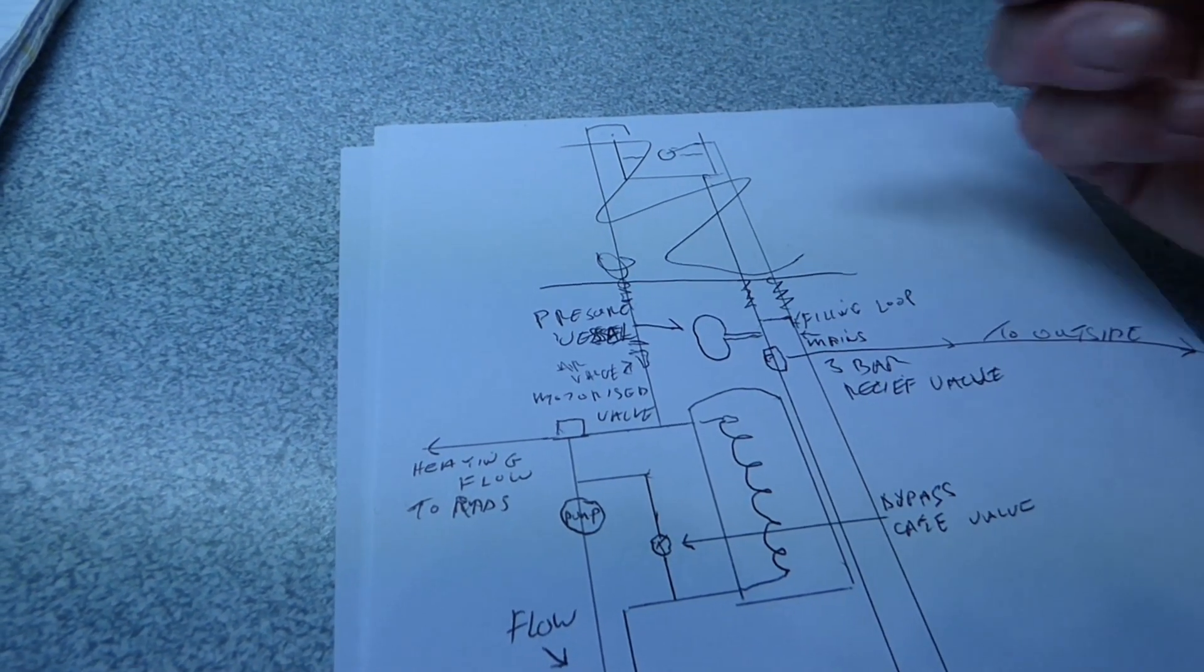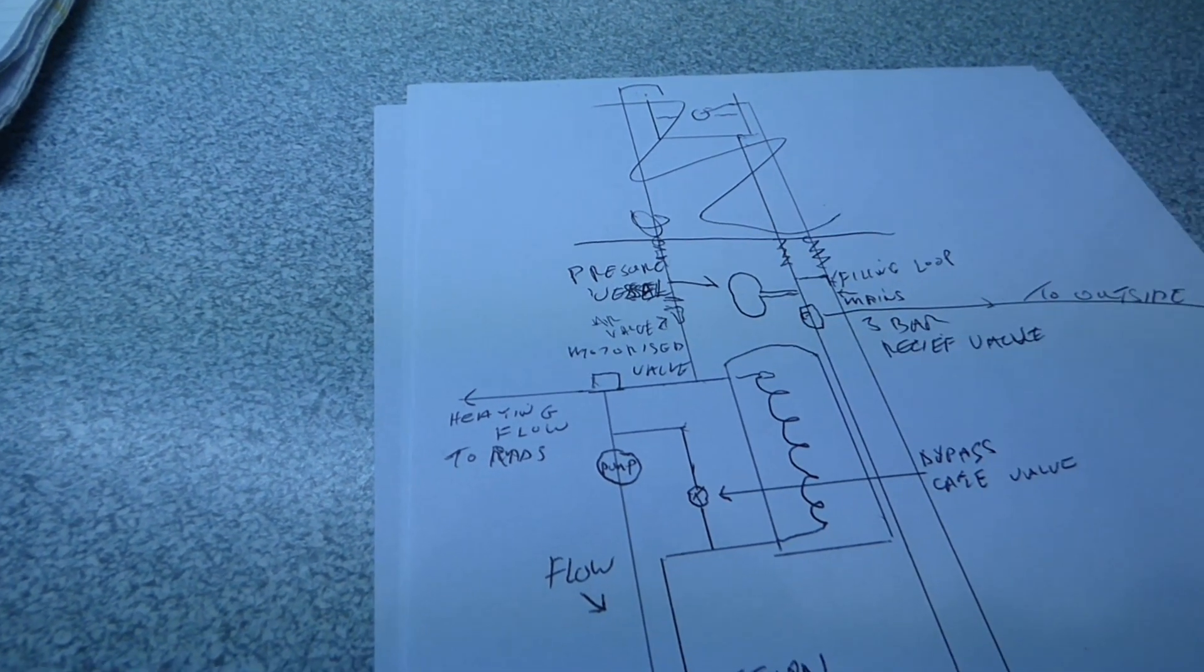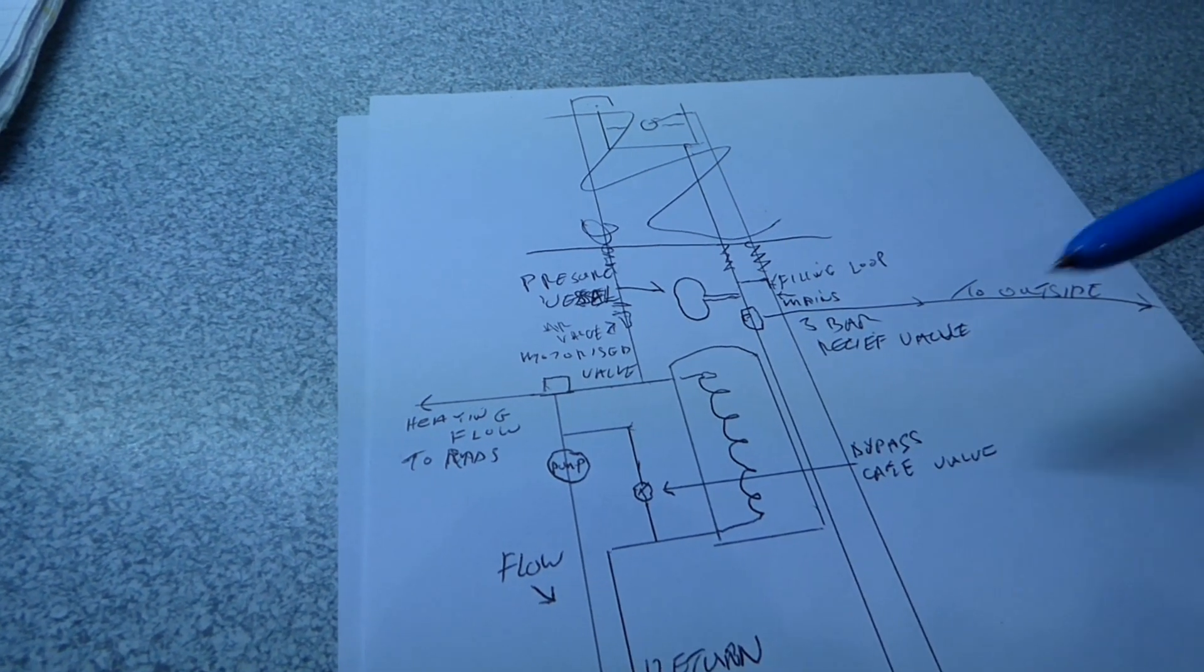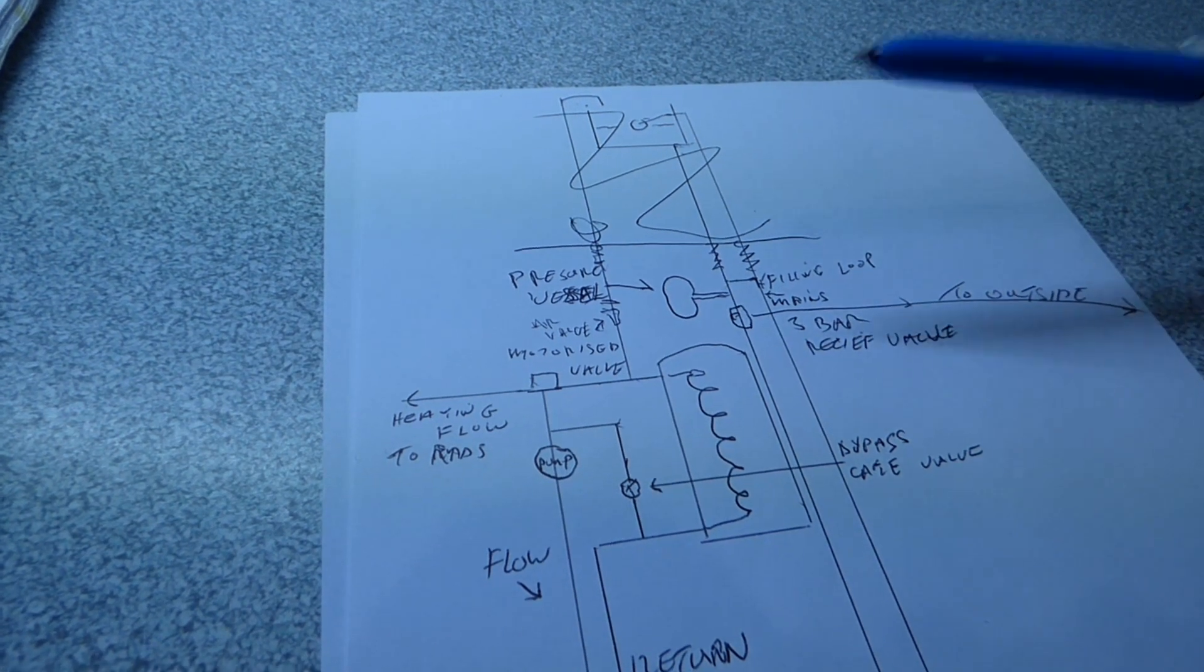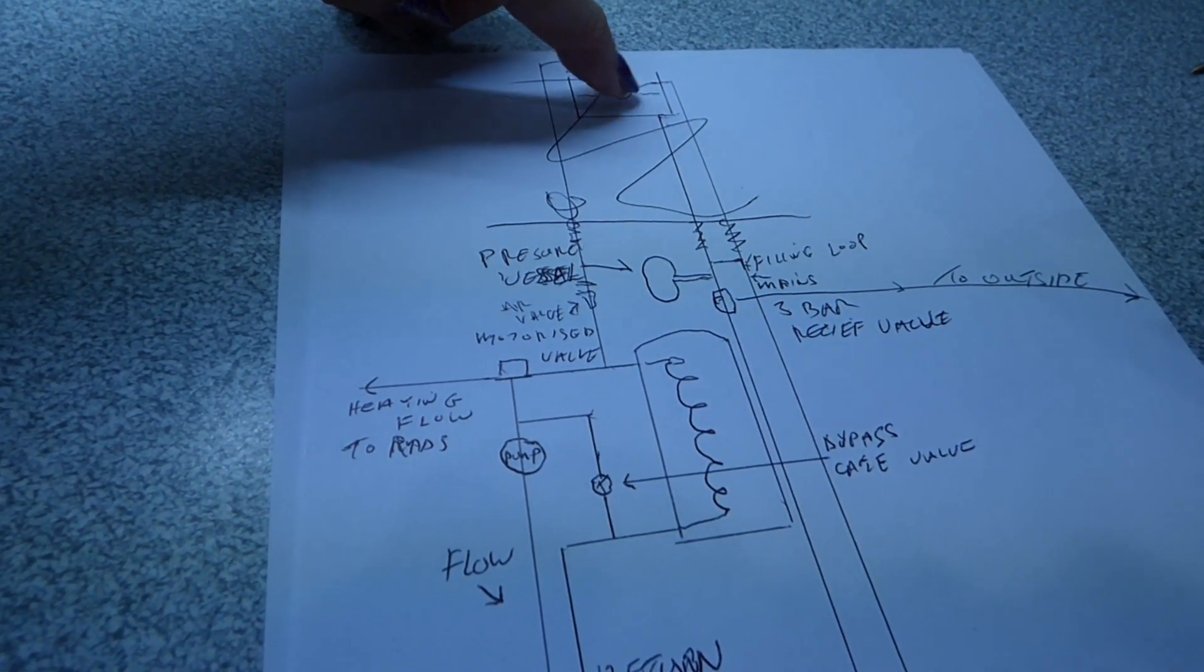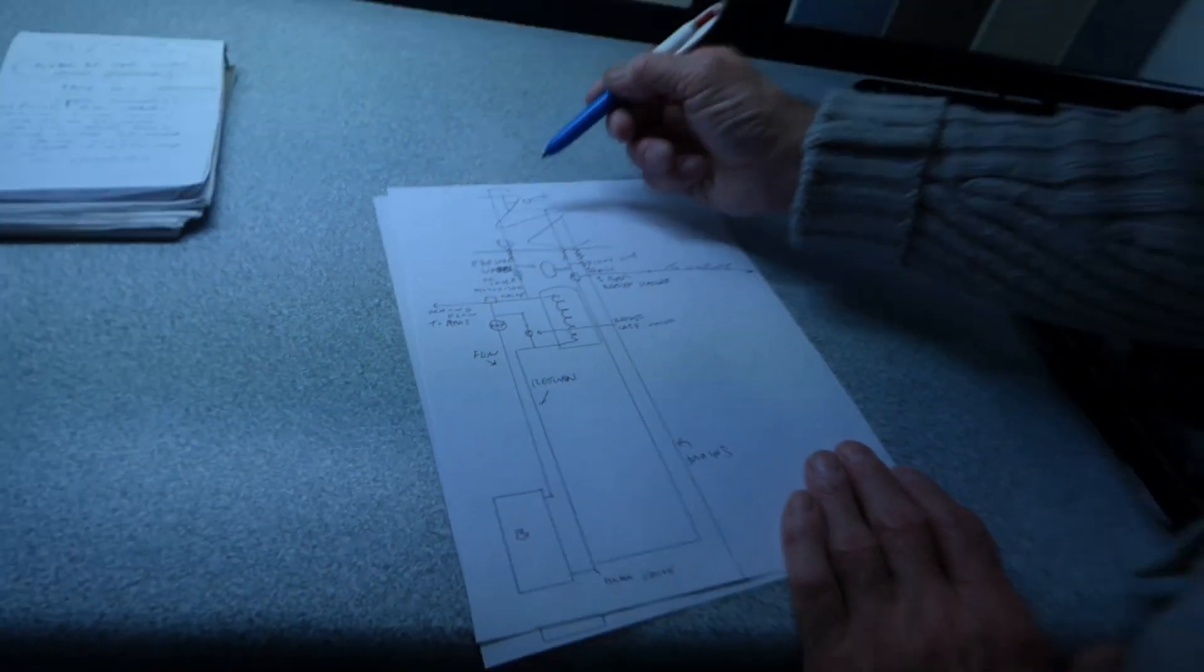So that takes care of all those pipes, all that. But obviously I wouldn't suggest you try and do it, it's probably best to get a plumber in to do it. But if you've got long-term problems with air and it keeps coming back, this is another way of getting over the problem. So why did they have a tank here with the water coming in in the very first place? That's an old idea, yeah, they called it an F&E system feed tank, an expansion pipe, and it's just a way to keep topping up the heating as it gets expanded and used. Obviously with a pressurised system, you will have to keep pressurising it every so often, and obviously if you've got any leaks anywhere, they must be fixed and sorted out, so if you're worried about leaks and possibly maybe the pipes not being up to taking a little bit more pressure, then obviously don't do that system. This is kind of like a do-or-die system when you've quite had enough of air, you want to get over the problem. But as I say, it's not for everyone, and some boilers won't be suitable for it, but it's just another idea I'm putting to you out there.